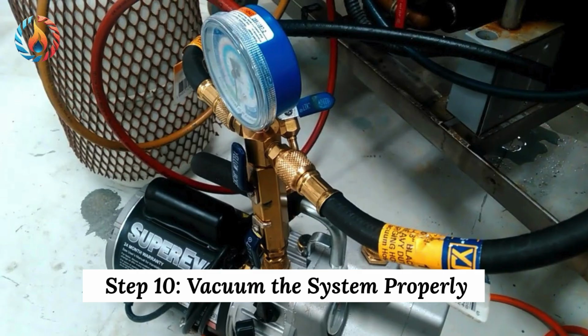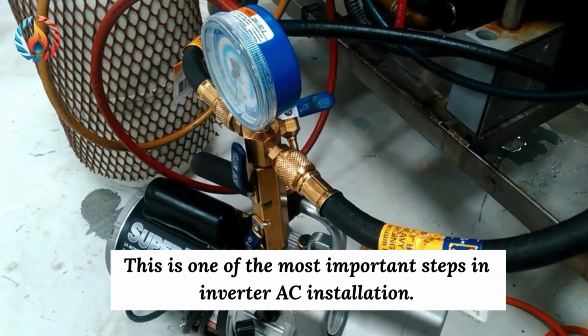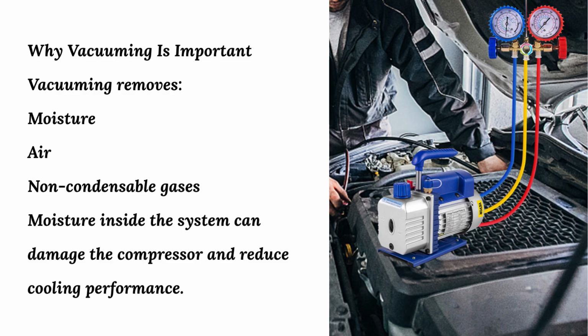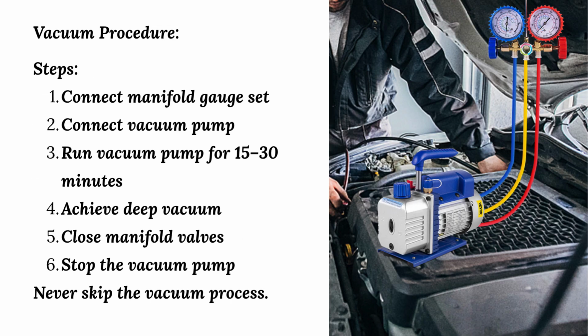Step 10. Vacuum the system properly. This is one of the most important steps in inverter AC installation. Why is vacuuming important? Vacuuming removes moisture, air, and non-condensable gases. Moisture inside the system can damage the compressor and reduce cooling performance. Vacuum procedure. Steps. Connect manifold gauge set. Connect vacuum pump. Run vacuum pump for 15 to 30 minutes. Achieve deep vacuum. Close manifold valves. Stop the vacuum pump. Never skip the vacuum process.